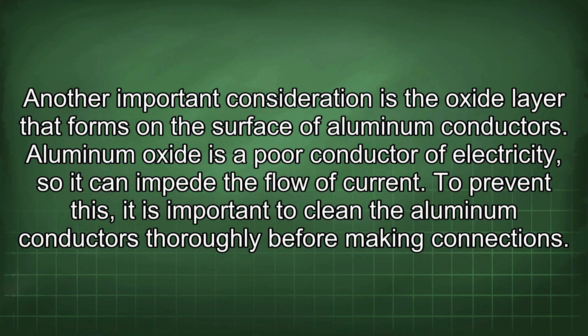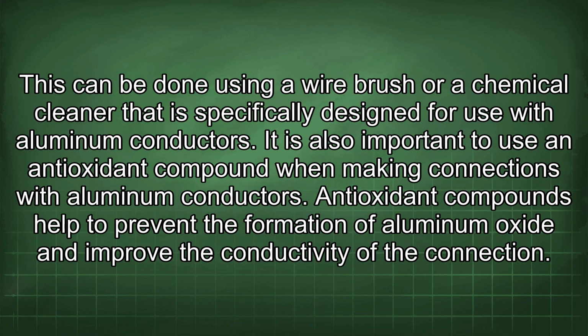Another important consideration is the oxide layer that forms on the surface of aluminum conductors. Aluminum oxide is a poor conductor of electricity, so it can impede the flow of current. To prevent this, it is important to clean the aluminum conductors thoroughly before making connections. This can be done using a wire brush or a chemical cleaner that is specifically designed for use with aluminum conductors. It is also important to use an antioxidant compound when making connections with aluminum conductors. Antioxidant compounds help to prevent the formation of aluminum oxide and improve the conductivity of the connection.